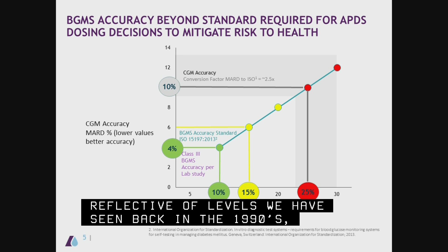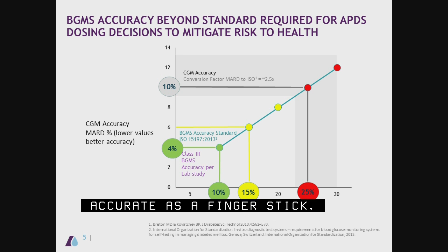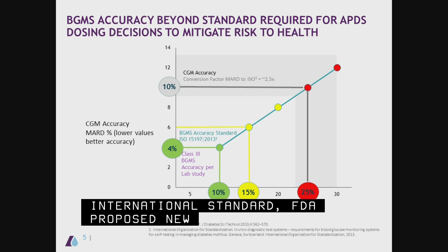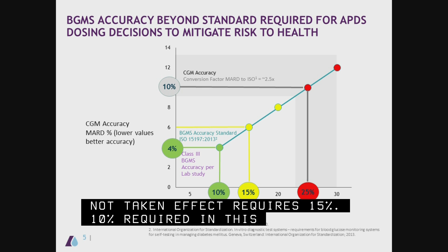For comparison, the international standards and FDA proposed new standards that have not yet taken effect require 15%, but 10% would be what's required in this artificial pancreas system, which would correspond to about a 4% MARD. So much more accurate than a CGM device would be standing on its own.